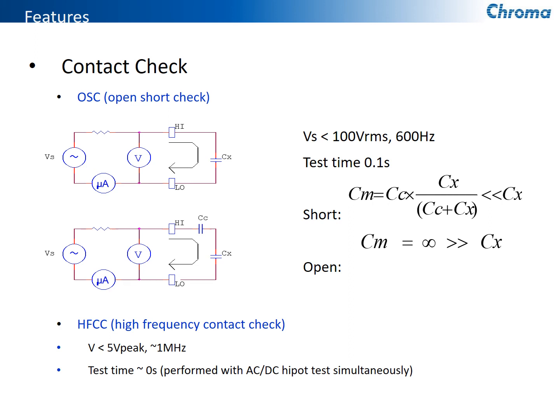device that's under test, where you would be using it for a high pot test where you're not physically connected to a conductor, but each winding that has an insulation between it. And when you have two windings with an insulation between them, they have stray capacitance. So what we're doing is we're looking for that stray capacitance to determine that we physically are connected to the proper unit to be tested.